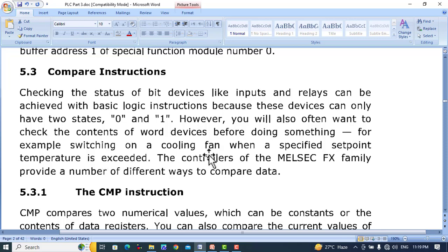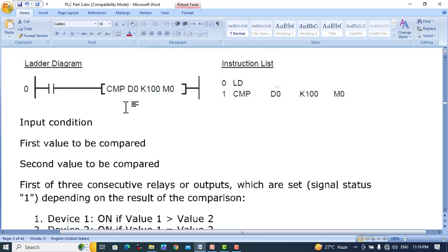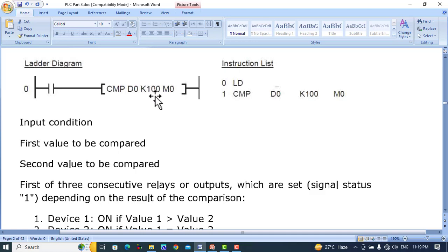For example, switching on a cooling fan when a specified set point temperature is exceeded. The MELSEC family provides a number of different ways to compare data. CMP is the comparison instruction used to compare data — whether greater than, less than, equal to, or not equal to. Here is a program showing how to use this instruction. The input triggers CMP; D0 is the first data source, which is compared with K100, and the result is stored in M0, M1, and M2.